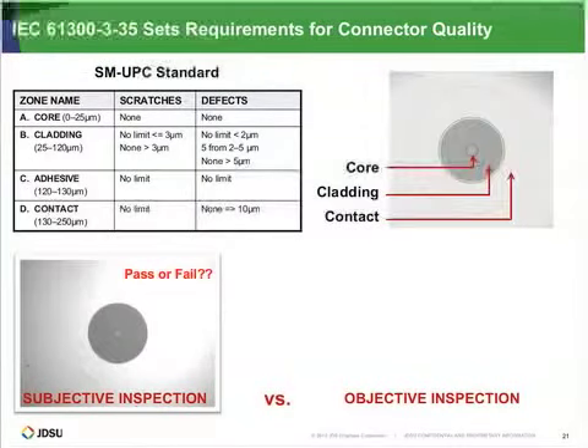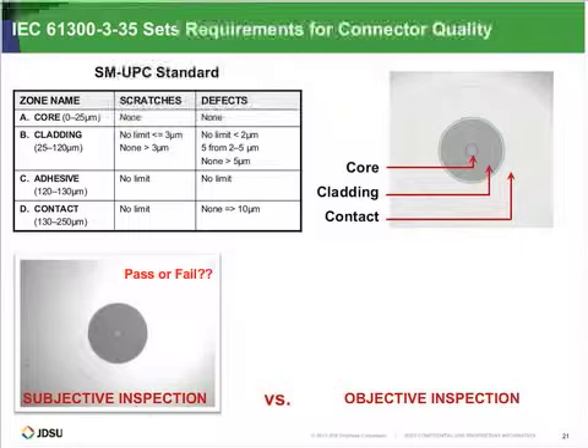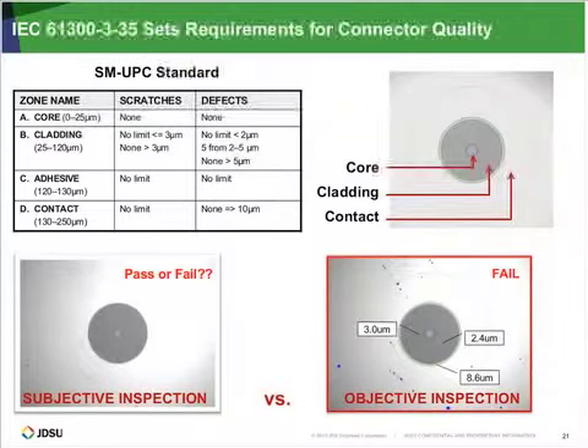What's also important in this environment is to be objective about the inspection. So the connector on the bottom left, is this good or bad? If you actually subject it to the standard, you'll find there are enough defects on this to fail it. With a digital microscope you can set the standards any way you wish, but a good place to start is the IEC standard.